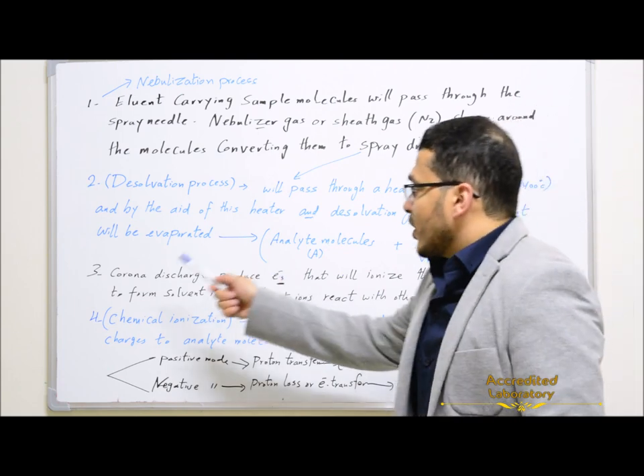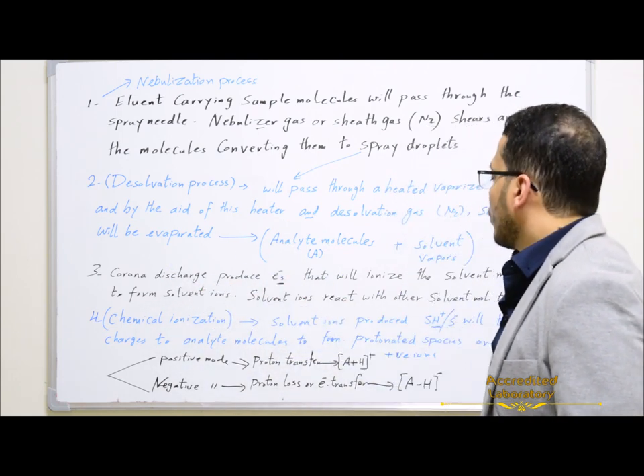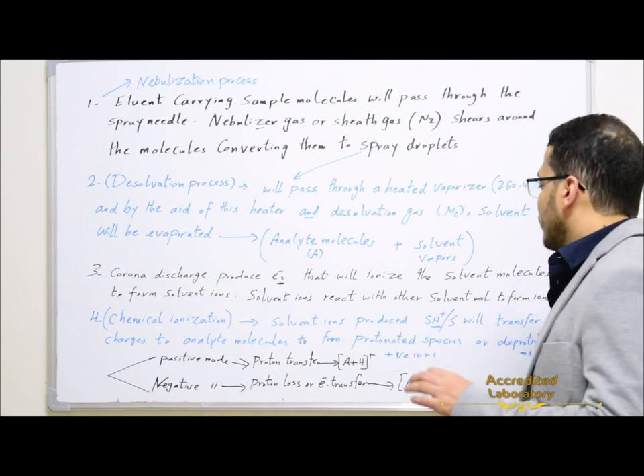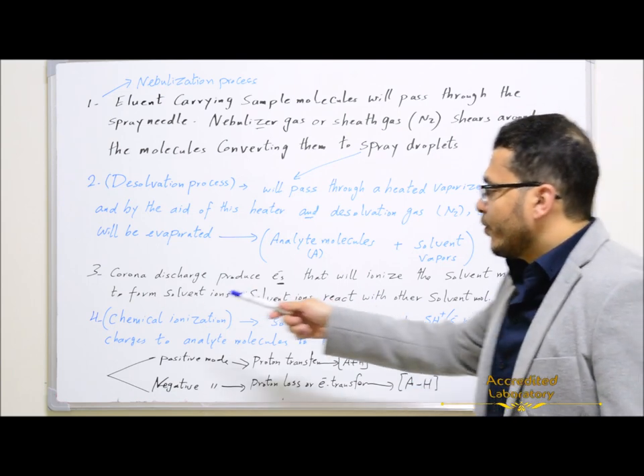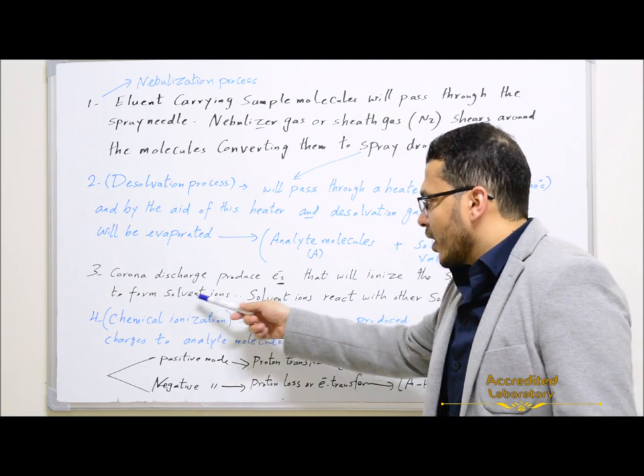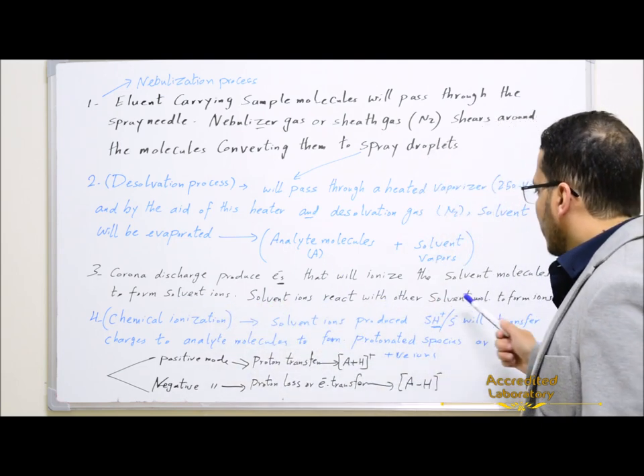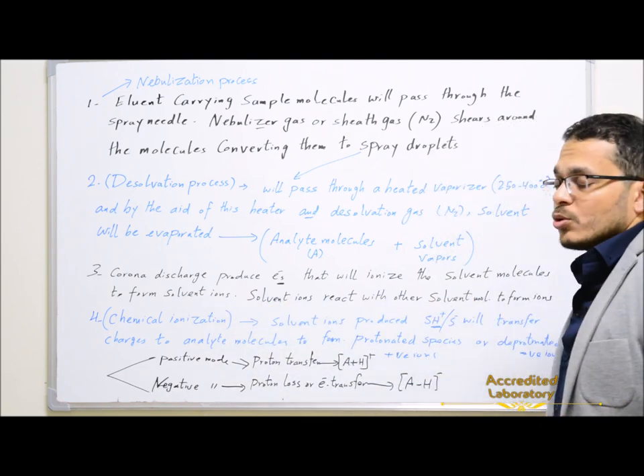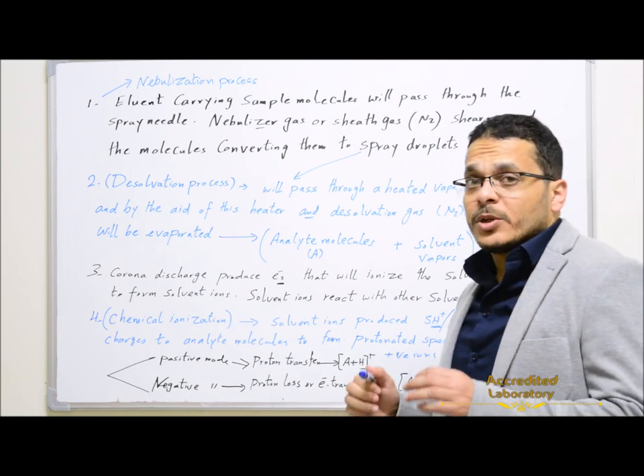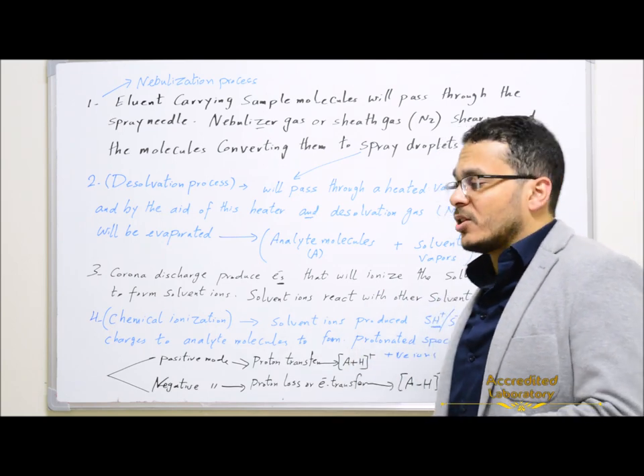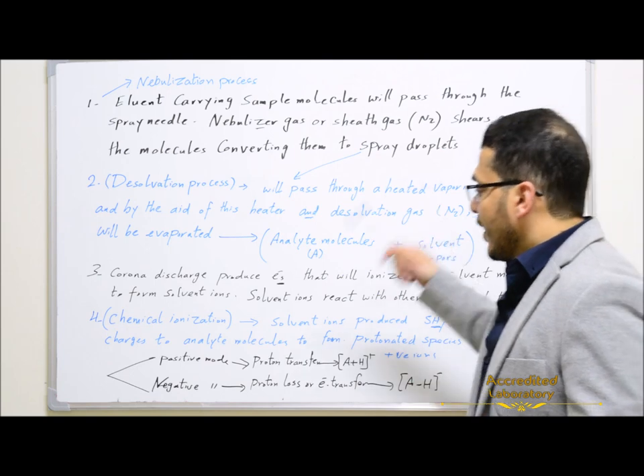Corona DC discharge produces electrons that will make ionization for the solvent molecules to form solvent ions. Solvent ions then react with other solvent molecules to form more ions, so solvent molecules should be present in higher concentration than analyte molecules.